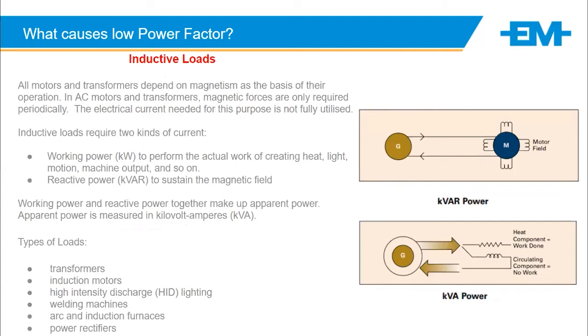Then what causes the bad power factor is what we call inductive loads. So inductive loads would be items such as motors and transformers. An inductive load requires two kinds of currents. It uses kilowatt to perform the actual work, and then reactive power to sustain the magnetic field. So if we look at this image here on the right, G is my generation, my utility, and then I've got a motor.